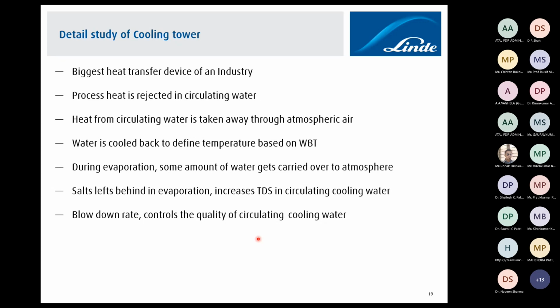And why do we need to maintain those total dissolved solids? Because a high amount of solids can deposit in the low velocity areas of the various heat exchangers, and as day by day accumulation starts, it affects the heat transfer, and then over a period of time it will reflect in the intended processes also. So it is not only the duty of the process engineers who are running the plant to maintain heat exchangers up to date, but more responsibility lies with the person who is operating the cooling tower and assuring quality cooling water in the circulating water. This is how you can really enhance the life cycle of your heat exchangers and all the equipment connected to the cooling tower.